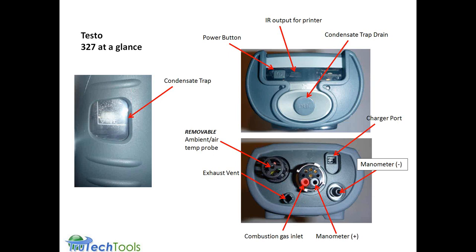The combustion gas inlet is over here on the right and the left, and the exhaust vent, after the gases have been consumed by the analyzer, analyzed, they're pumped out here at the bottom of the meter. And then this removable ambient air temperature probe we talked about before stays in the meter normally. It can be replaced with another temperature probe if you so desire.